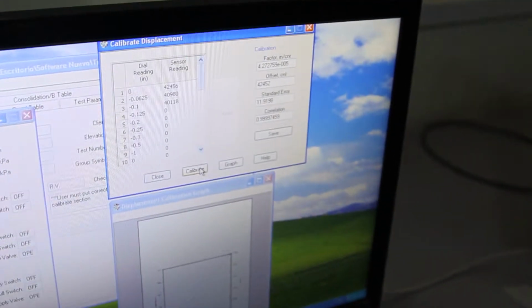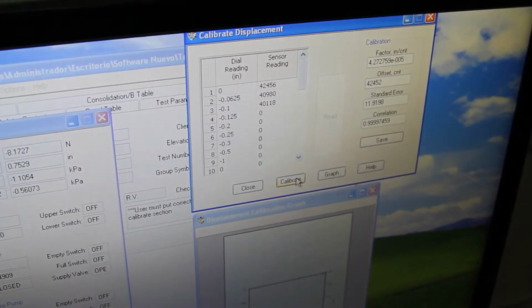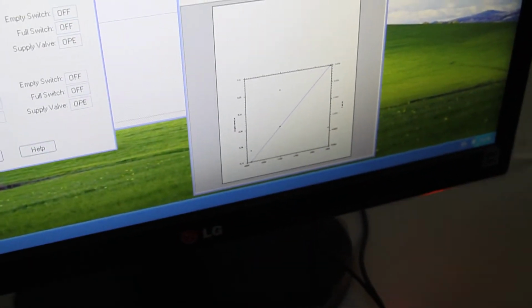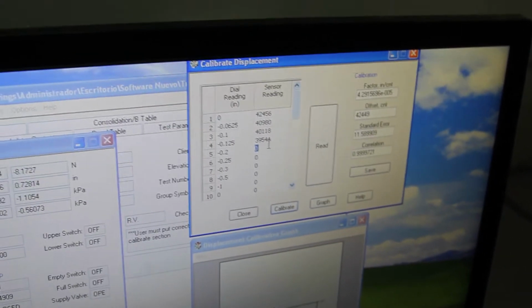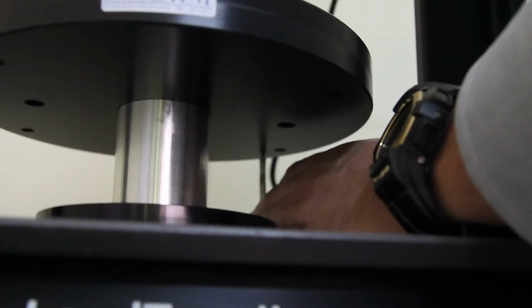The next one is 0.1. And so now I have the next point. So I go back to my software and do read again. So now I have 3 points. Do calibrate. So I can see my calibration taking place. Then again, I'm going to repeat the process. I'm going to remove my third point and put the next one, which is 0.125, underneath, and go back to the software to the same line and do read and calibrate so I can check what's going on. Again, I will remove my third point and put the next one.